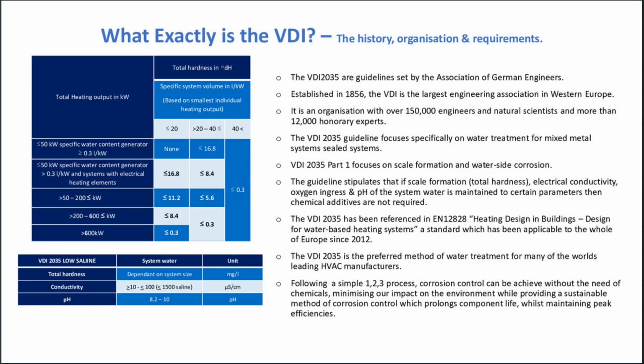The VDI 2035 guidelines focus specifically on water treatment for mixed metal sealed systems. Part 1 focuses on scale formation and waterside corrosion. The guidelines stipulate that if scale formation - so total hardness, electrical conductivity, oxygen ingress and pH of the system water - is maintained to certain parameters, then chemical additives are not required.